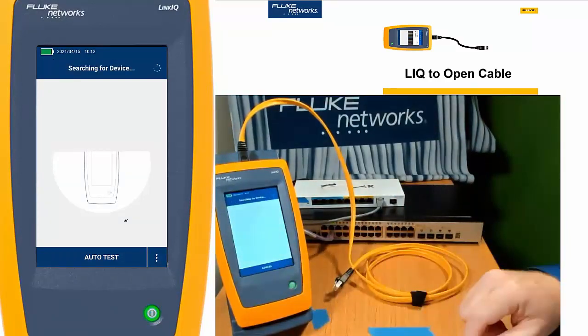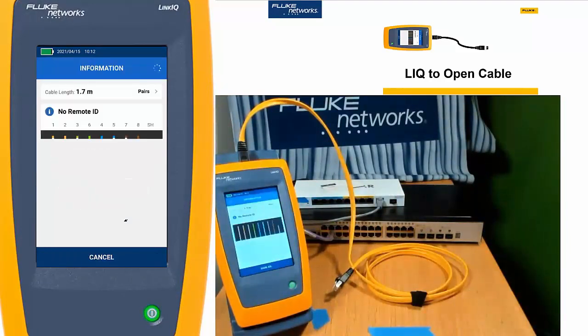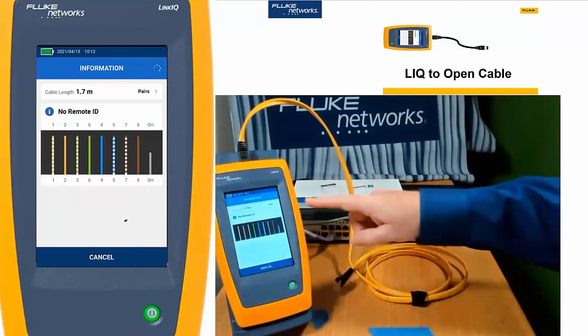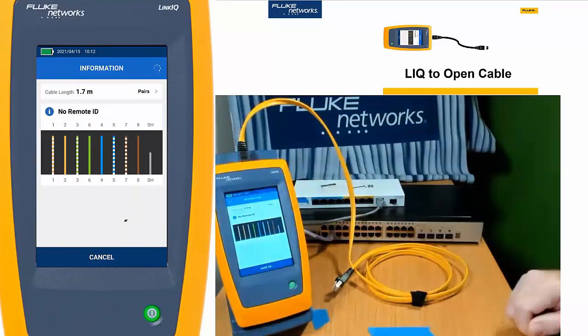Well, I'll just push auto test and it's going to run and it's going to tell us this cable is open about 1.7, about 5 feet away. Great, that's very helpful. Another situation that we come across is where somebody is installing cables.